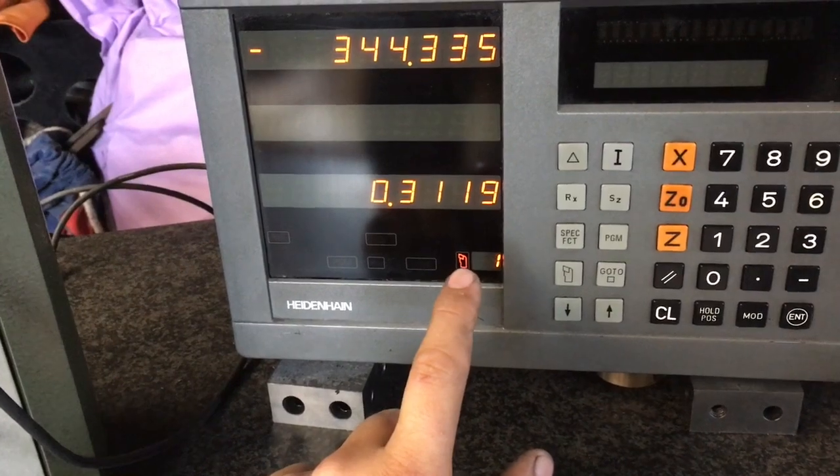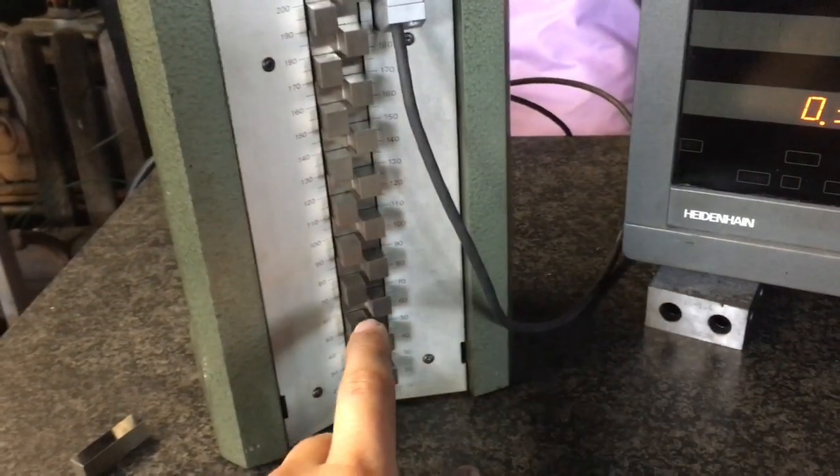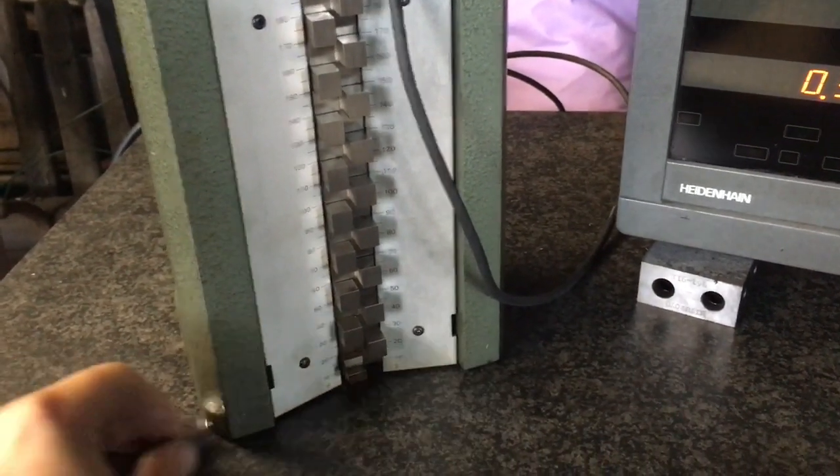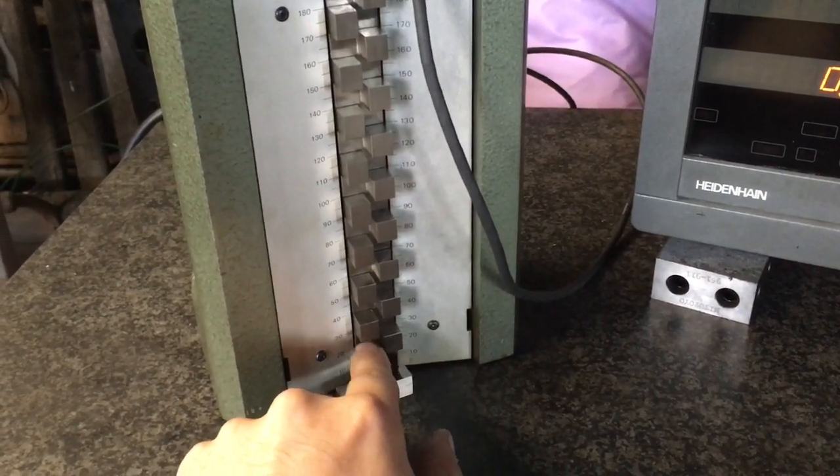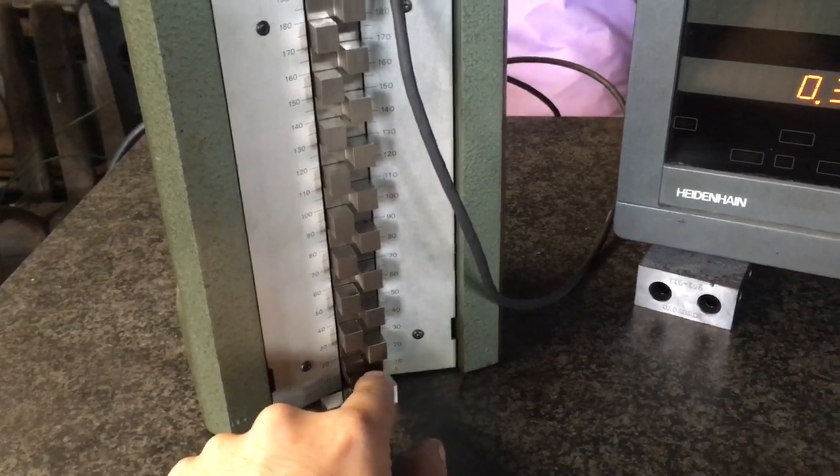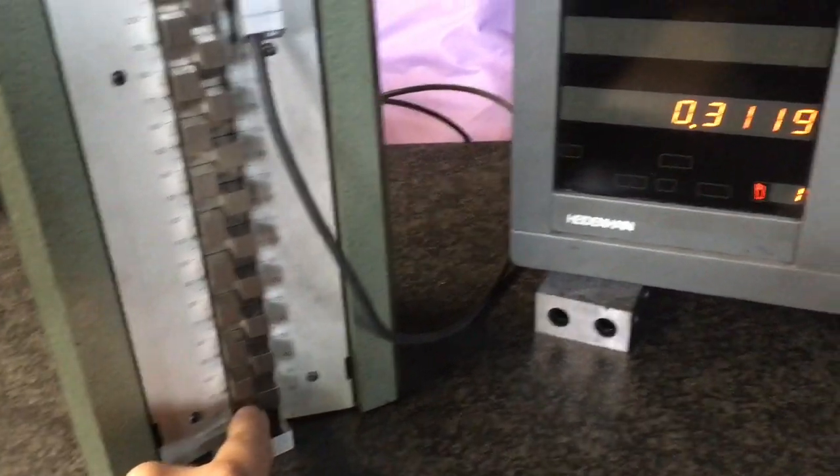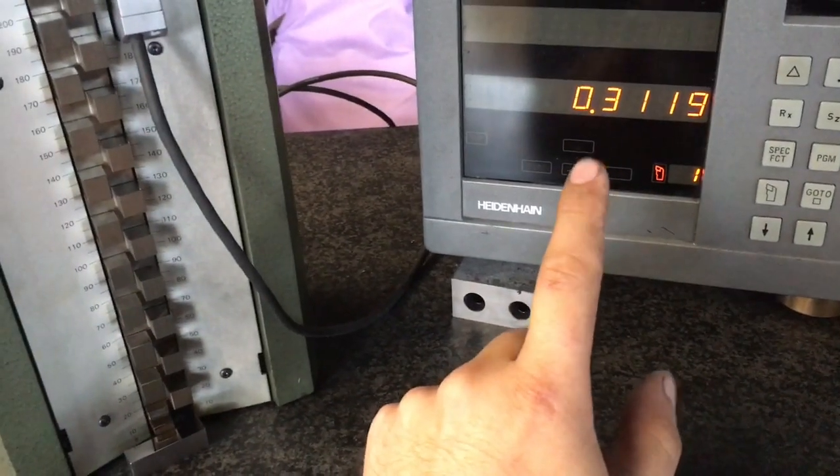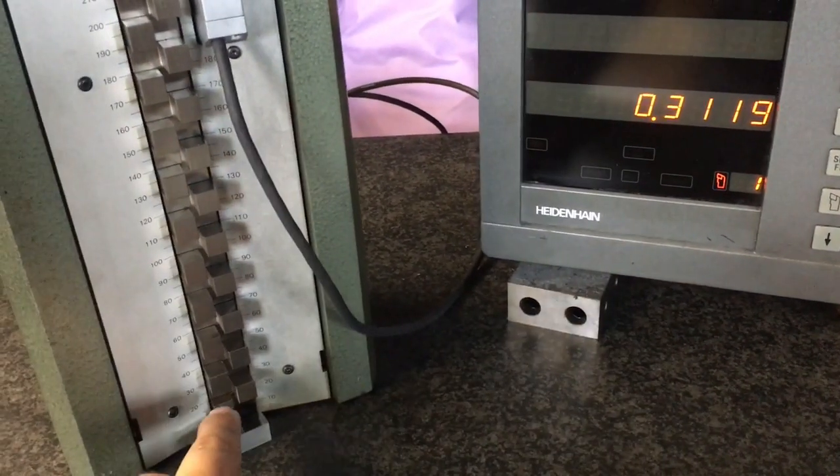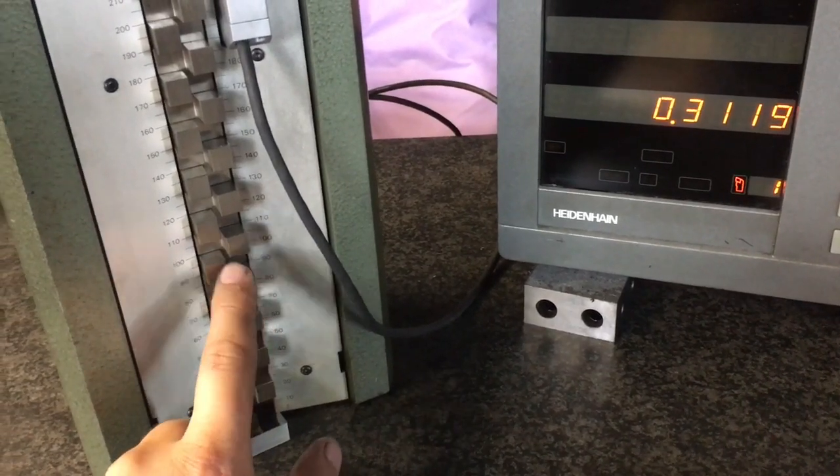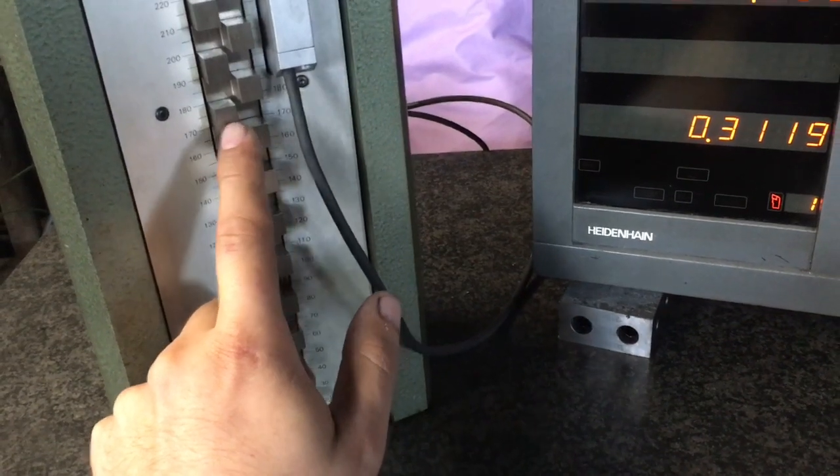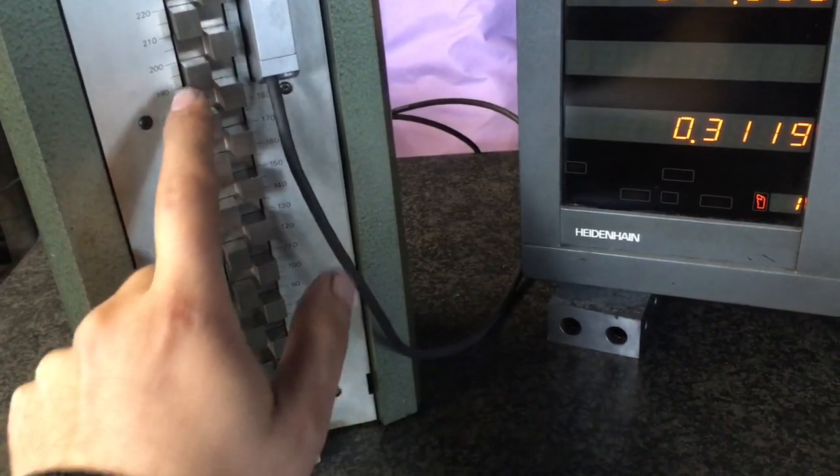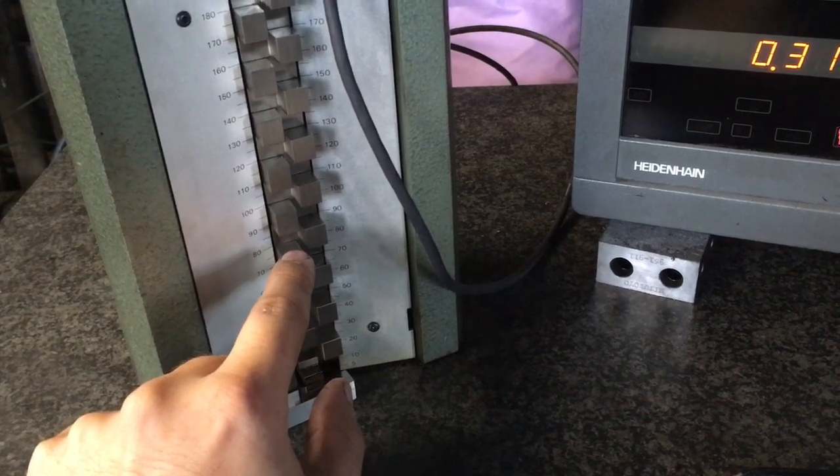That's kind of what we want here. When we put the 11 millimeter gauge block here and we reference on this gauge block, then we can call offset number one, call in 11 millimeters which is our absolute datum. And then have one offset for every single gauge block. With calibration you can also add up the calibration error. Most of the time you ask for a point in the center when you do the calibration, so when you probe, you probe on the center.